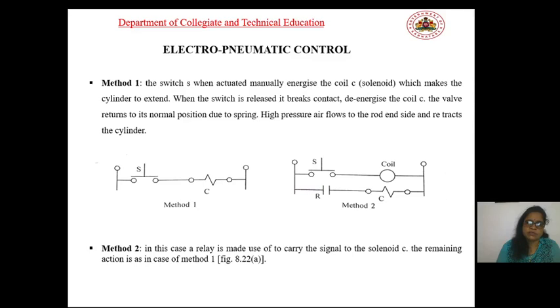As you can observe from Figure 1, when the switch S is actuated manually, the coil C (solenoid) gets energized, which makes the cylinder extend. When the switch is released, it breaks the contact and de-energizes the coil C. The valve then returns to its normal position due to the spring.